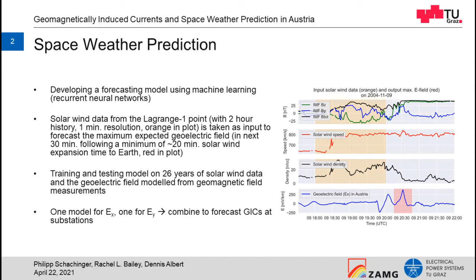The calculation of GICs starts with the calculation of the geoelectric field. In our case, this is either done by defining electric field scenarios or by using the plane wave method with 1D Earth models and geomagnetic field measurements. From power grid data, we create a power grid model, which leads in combination with the electrical field to driving voltage sources for each substation.